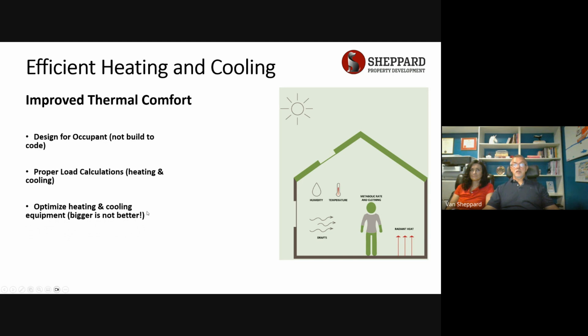You want to optimize your heating and cooling equipment, and that's a follow-on from proper load calculations. Once you know how much heating and cooling you need in your building, make sure you're sizing your equipment to provide that. And bigger is not better. If your calculation says that a room needs 4,000 BTUs of heating, and you say to yourself, well, the smallest heater I can get that goes in there, let's say you're going to put a heat pump heater in there, and you can get them from as small as 7,000 up to 15,000, you say, well, I'm going to put a 15,000 BTU unit in there. You're not servicing yourself with that. You want to put the equipment in there that's sized properly for the room.